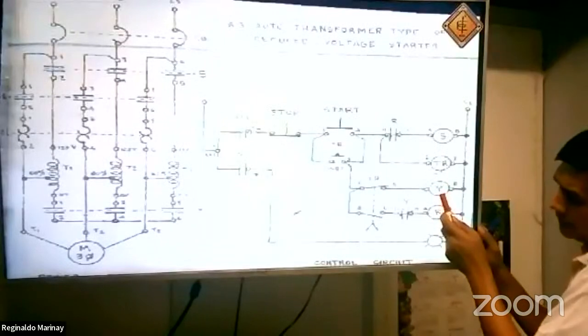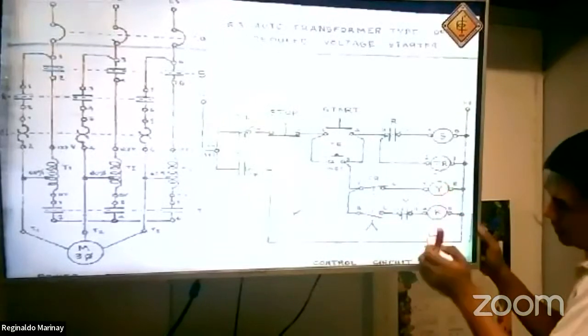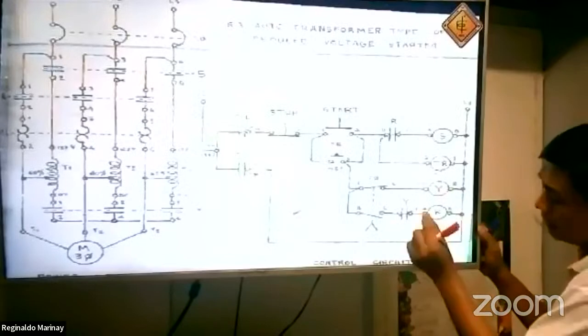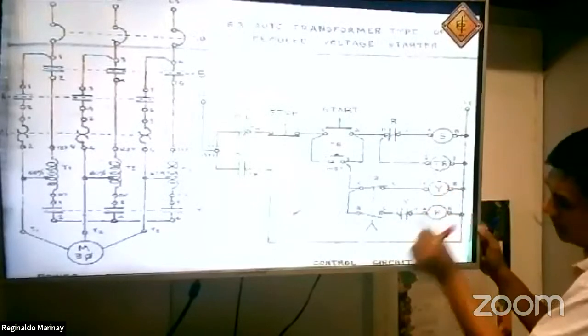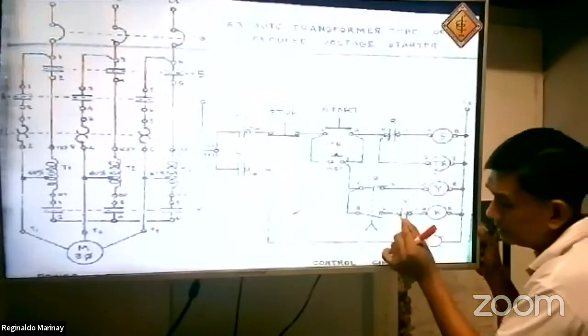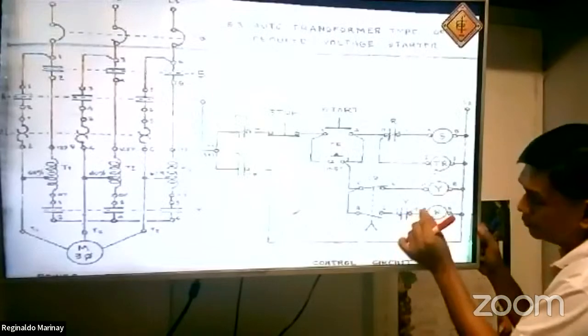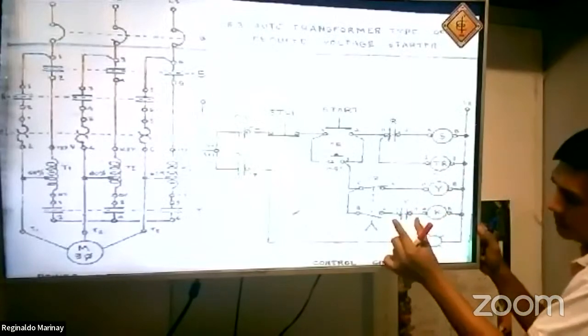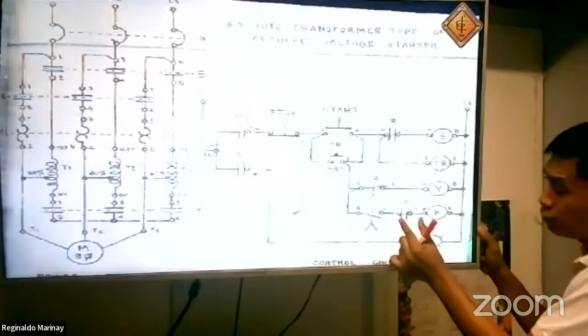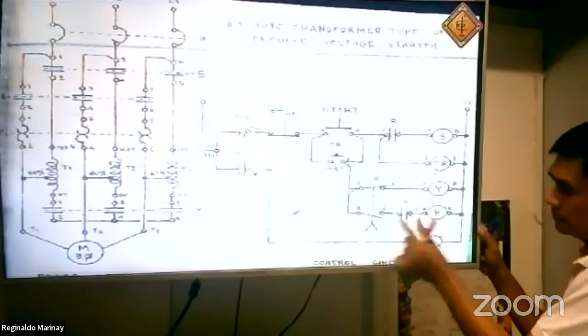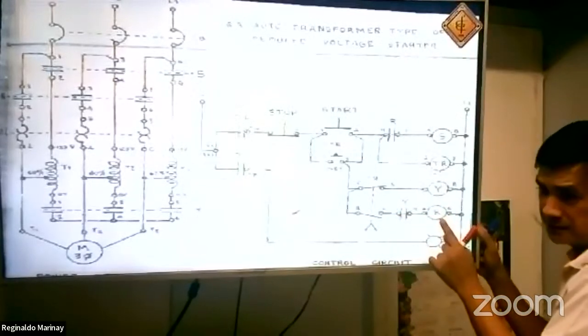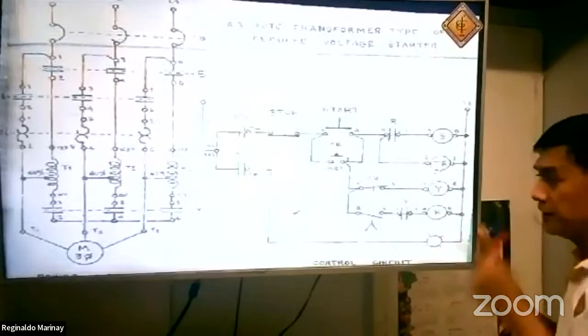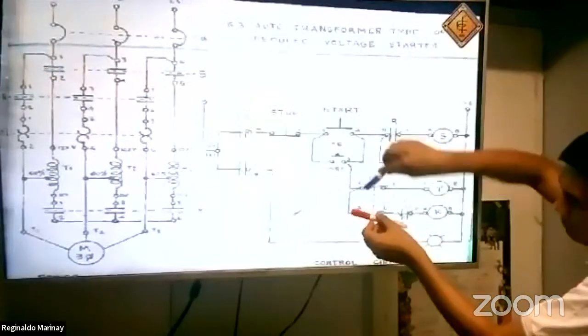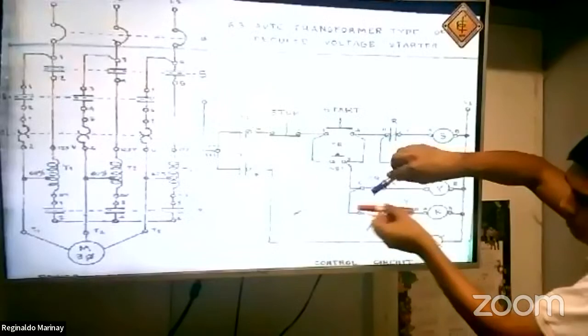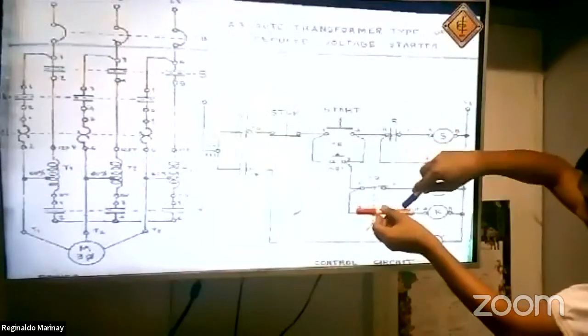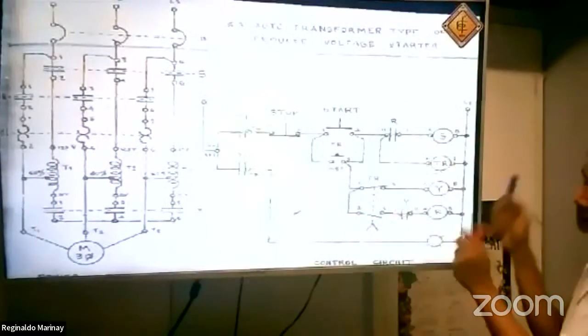This is open. By the way, there is an electrical interlock here. Once this becomes energized, the 11 and 12 will become open. This is assuring that this will not be energized. But once you reach 3 seconds, what will happen? This will become open, this will become closed. The current will flow here. Take a look here.